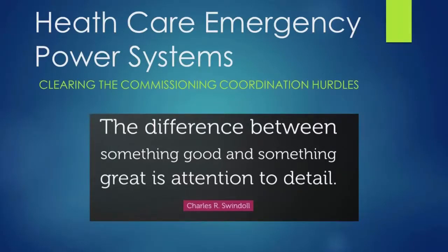Correct. Normally, if emergency power is part of our scope of work, individual components are tested—the generator, the ATSs, any emergency power distribution breakers, and so on—verified individually, then collectively building into a full emergency power supply system test. A drop of normal power is what we call a black site test, which is separate from the emergency power supply system test, and typically done after that test is completed.